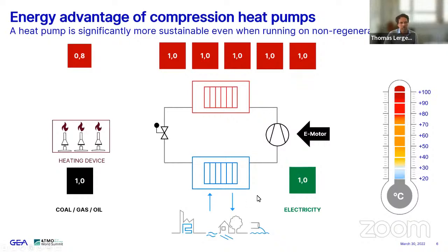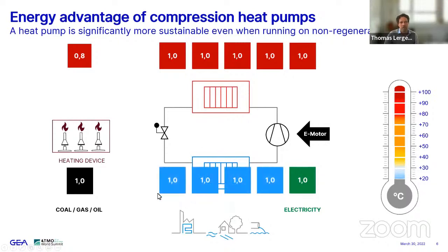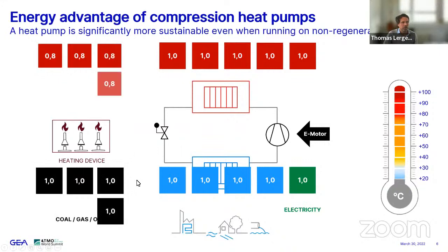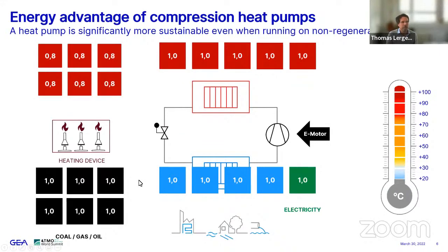That's possible because, as we've seen before, the heat pump uses heat from heat sources that are already there. So this is your balance sheet of a heat pump. And this heat that's coming into the heat pump is free of charge. It doesn't waste or use any resources, it just needs to be available. So if you want to have the same output with a classic boiler with gas or oil, you need to put in 6 units of energy, and then you still don't end up with the same amount of heating rating that your compression heat pump is able to provide.